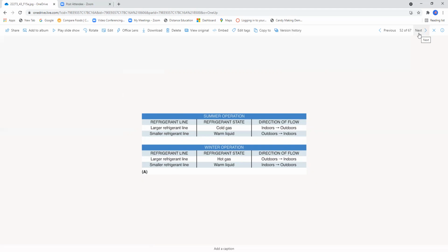And just bear in mind that if you don't have 2 ports necessarily on the outdoor heat pump section, you actually have a 3rd port so that you can check the pressures correctly in the heating mode as well as the cooling mode. If you do not put your gauge manifold hoses on the right access ports, you'll actually peg out one of them during the heating mode. There is a 3rd connection. I don't know if the slides here will show that 3rd connection. So you can actually look at the pressure-temperature relationship in the heating mode as well as in the cooling mode.